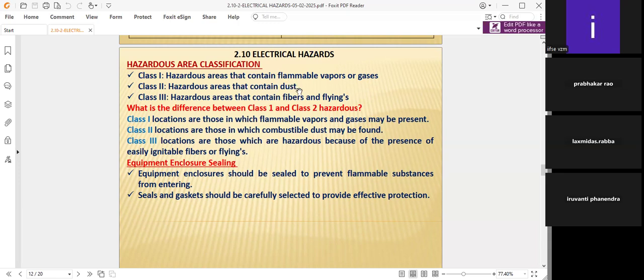The circuit itself is taken care of as a hazardous area, not like air dust and all. The process dust is where it becomes hazardous. Because if the dust extraction system is not properly run or not in proper condition, dust accumulates on the electrical equipment itself. Where electrical consumption is there, heat is generated, and thereby the dust becomes combustible. That's why a hazardous area is class 2, containing dust. What you said is 100% right.